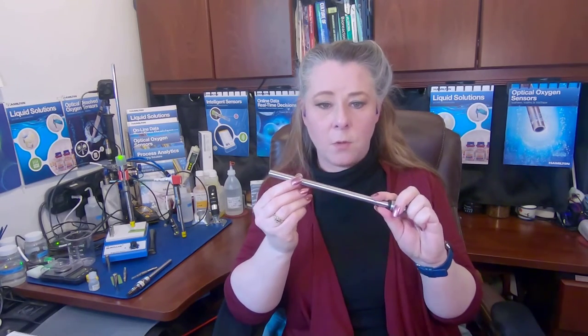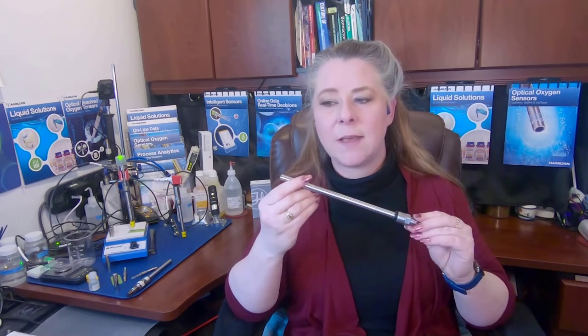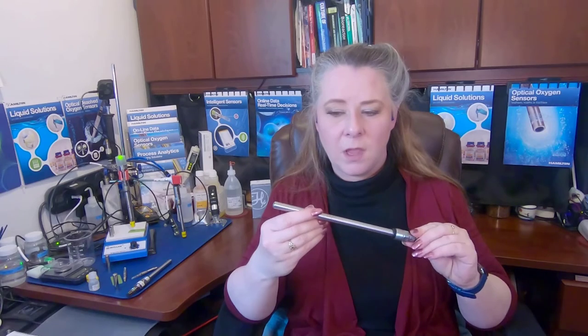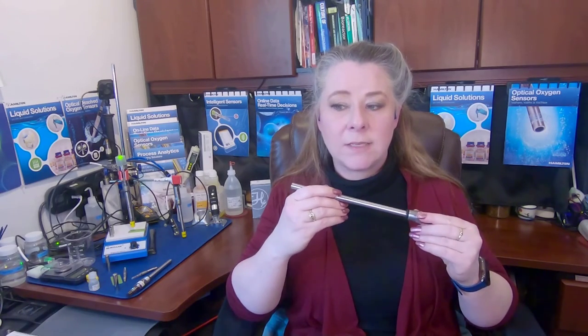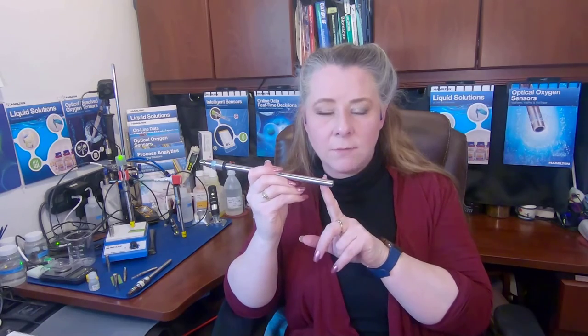It makes something called carbonic acid. And carbonic acid is going to change the pH of your media, which is why you are constantly measuring pH, and you're constantly doing things to tweak and adjust your pH and keep it within a certain range. That's really important to understand, because CO2 can also crawl inside of your polarographic probe where there's electrolyte, which is water-based. And as the CO2 goes inside, it can change the electrolytic strength or the pH of the electrolyte inside of the probe, which changes its ability to read a voltage signal. As it becomes more acidic, which is what happens with CO2, the ability of the electrolyte to read the voltage decreases.